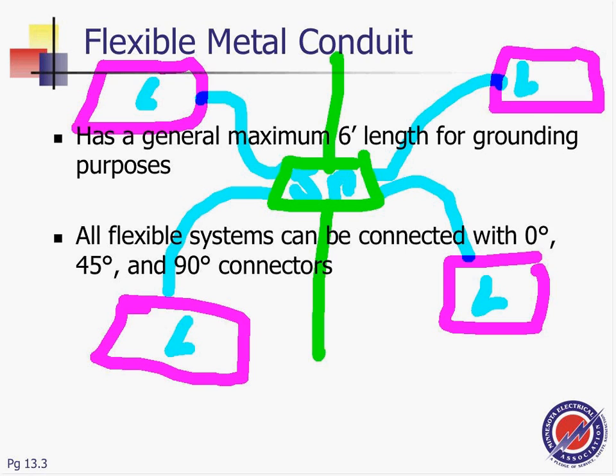Now, if your flex is 6 feet of fixture whip, 6 feet or less, and if the circuit coming in, guys, is 20 amps or less, so you have a lighting circuit, 20 amps or less, and the flex is 6 feet or less, then you do not need to pull an equipment grounding conductor. What that means is I do not need to pull right in here an equipment grounding conductor with each one of them. If it's more than 6 feet, then you need to pull an equipment grounding conductor, and that's for the fixture. So basically the flex can work as a grounding means up to 6 feet, flexible and or Liquidtight flexible metallic.